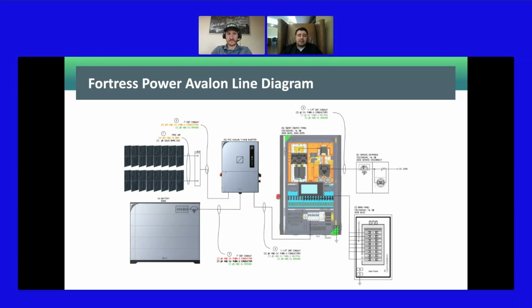DC coupled solar always goes to the inverter. In terms of AC coupled solar, if you have AC coupled solar, that means you already have the means to have the AC signal available from the solar production—that would be your solar inverter. You just take the cables, L1 and L2, from that solar inverter and land them on the main bus bar of the smart energy panel by means of a breaker. That's it—your AC coupled solar is connected to the SEP.